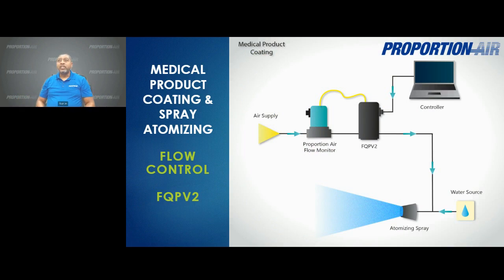In this application, an FQP-V2 proportional valve and an F-series flow monitor accurately control the flow of air in an atomizing spray and medical product coating application. The F-series measures the flow and provides a second loop feedback signal to the FQP-V2 to either increase or decrease the flow. As the pressurized air combines with the coating material, the material is atomized for spraying. It coats consistently and accurately.